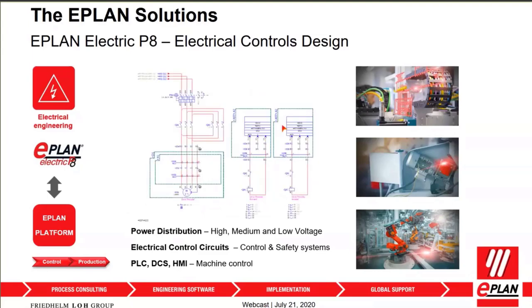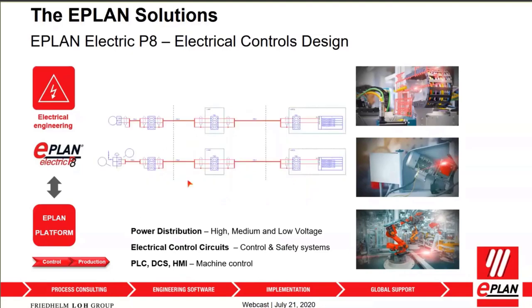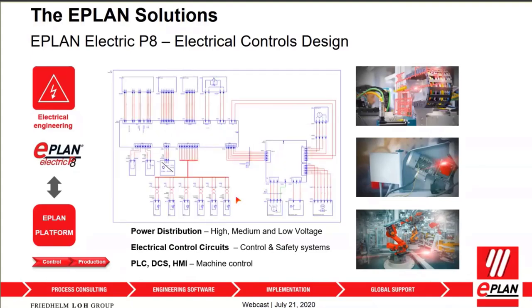You can represent a motor control in a functional view, showing IOs and your actuator on the same page — a very easy view to troubleshoot your system, knowing exactly which input and output control a given motor. P8 supports IEC layouts for European, North American, Russian (GOST norm), and Chinese (GB norm) markets with the right symbology and terminology. You can also design loop diagrams — if you have a P&ID designed in preplanning or imported via an instrumentation list, you can map data to loop diagrams and generate them through templates. Interconnect diagrams can be used for embedded systems or to create wire harnesses.